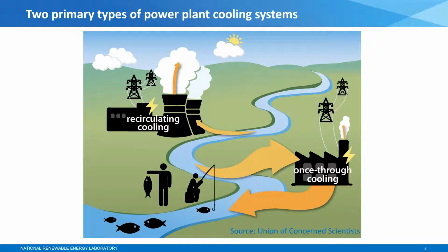The other type is once-through cooling, which withdraws water in large quantities and, through a heat exchanger, recondenses steam, then discharges that water back into the water body at a slightly higher temperature. There are also other types of cooling systems, such as dry cooling or pond-cooled systems, which can be a hybrid of these approaches. I'll focus mainly on recirculating and once-through, but dry cooling systems are relevant because they can accomplish the same cooling needs, sometimes at a cost and performance penalty.